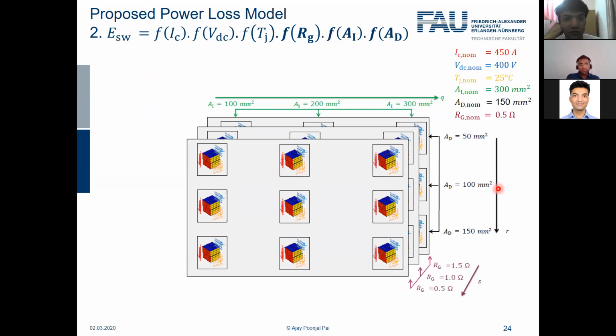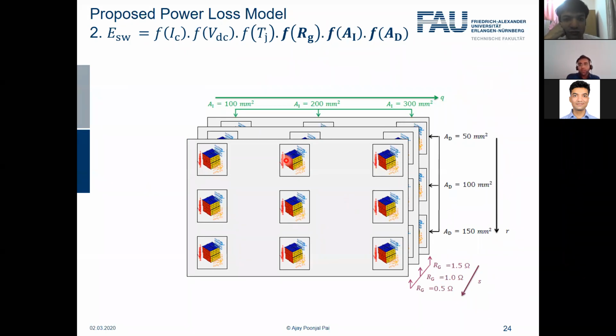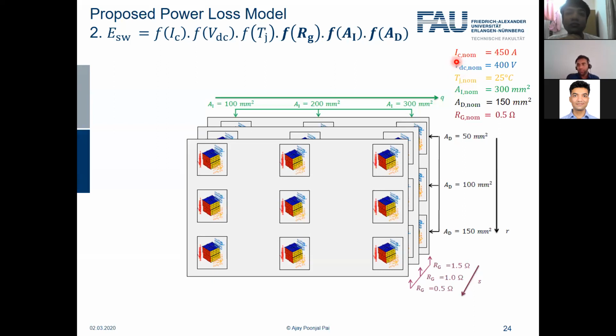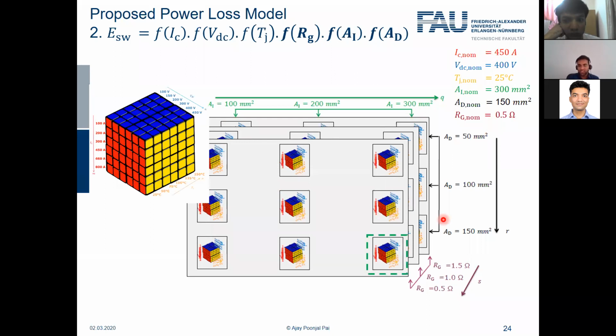So then, what we do in this approach is define nominal points, or nominal values, for each of the parameters, as you can see here. So I define, for example, for the collector current, 450 ampere as the nominal point, DC link voltage 400 volt as the nominal point, and so on. This means now I don't need to characterize all of these Rubik's cubes. I can look only into the Rubik's cube represented by these nominal points, which is this one.